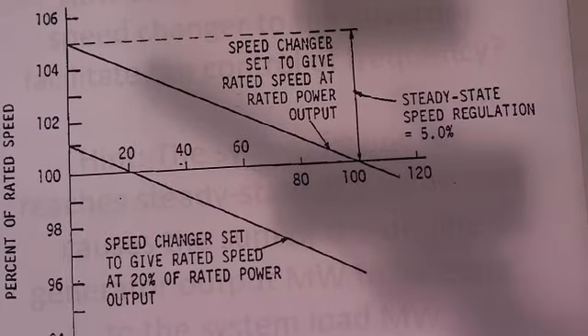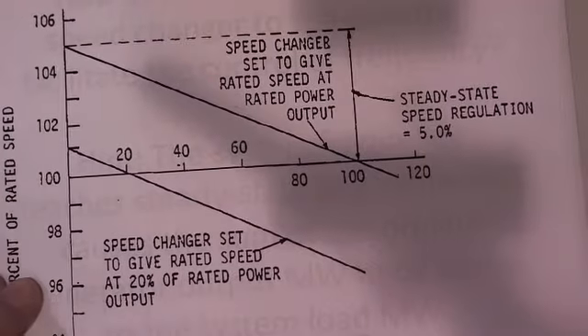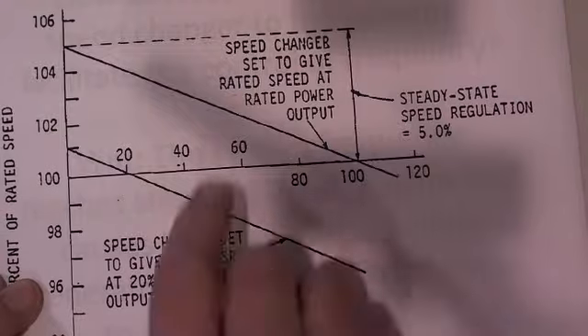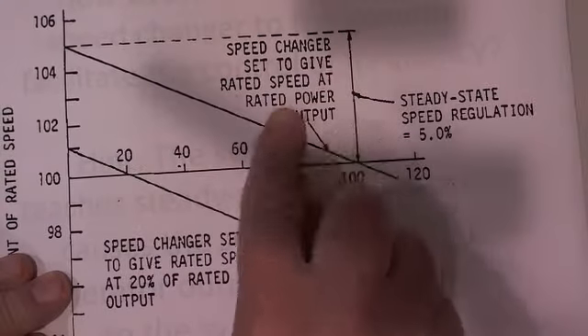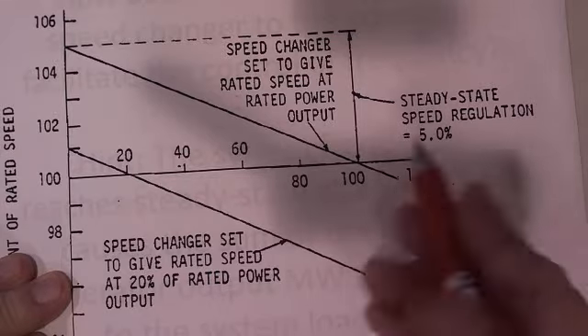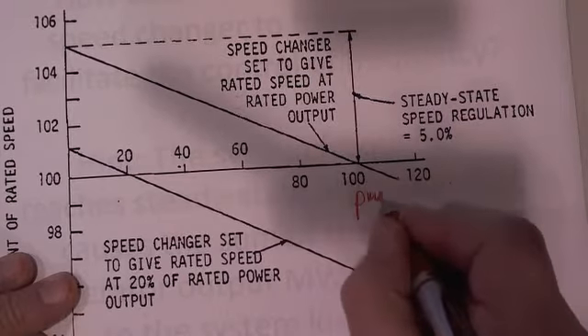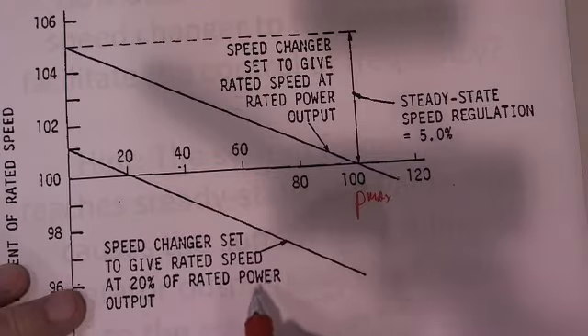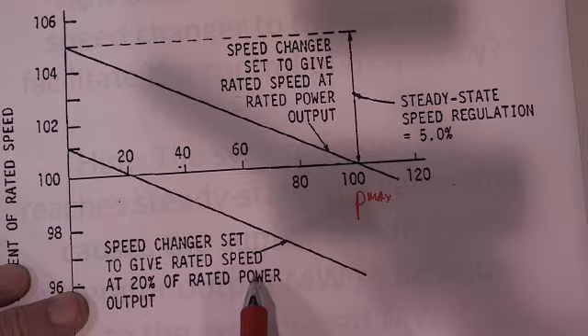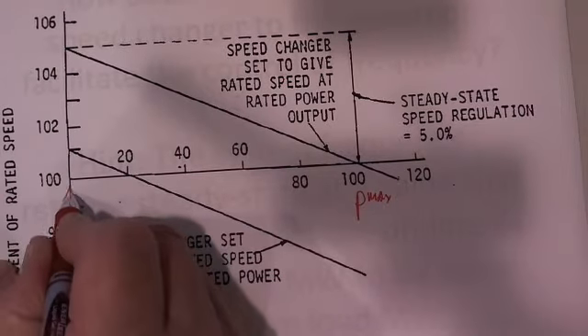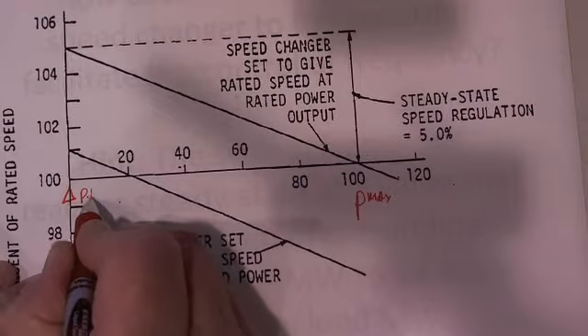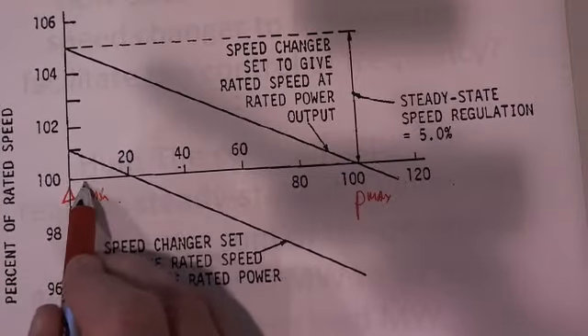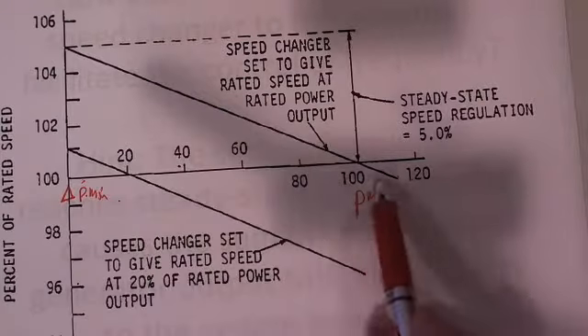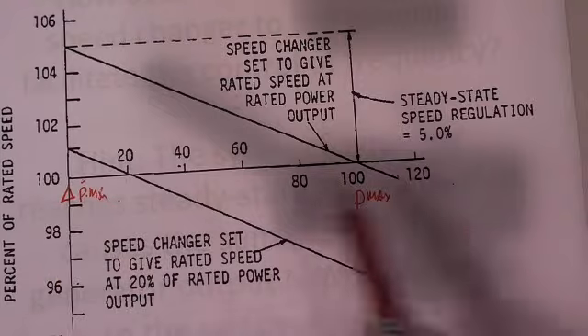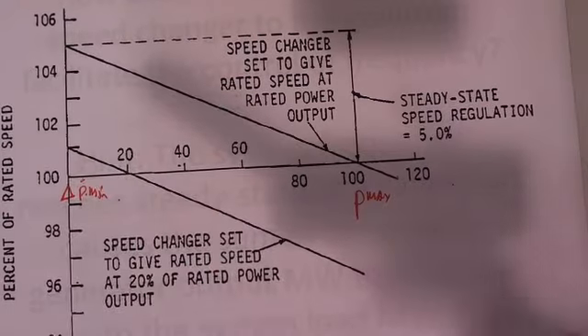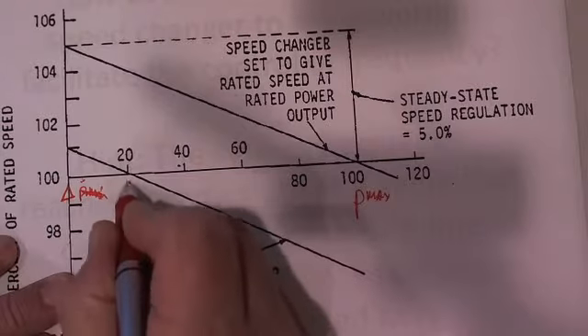So, power output as a function of frequency, they call that the speed changers. It's set to give rated speed at rated output. Rated output simply means that this is P max over here, and the speed changer is set to give rated speed at 20%. So this thing pretends that this is P min over here of 0, but the truth is it's not going to be 0. Here it is, 20% of the max. Probably you don't let the thing operate much below 20% anyway, so I should simply say that's the P min.